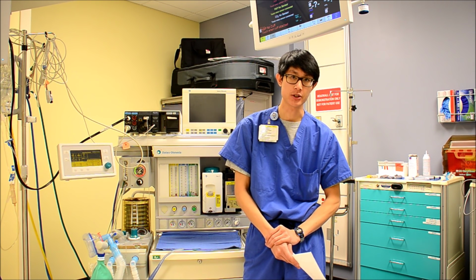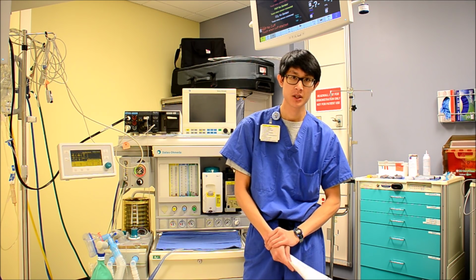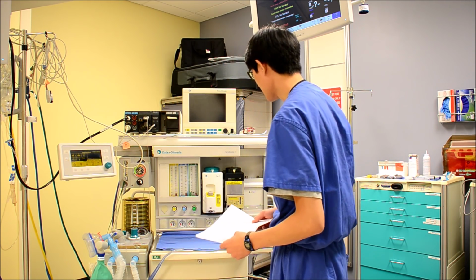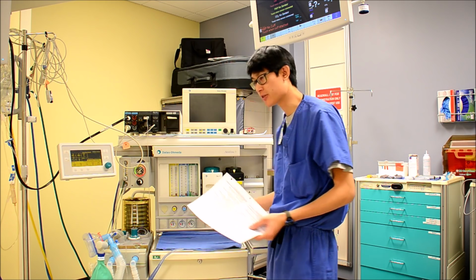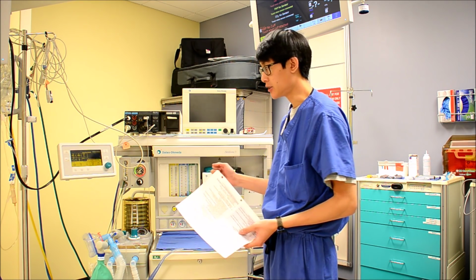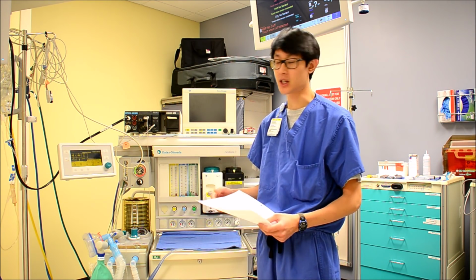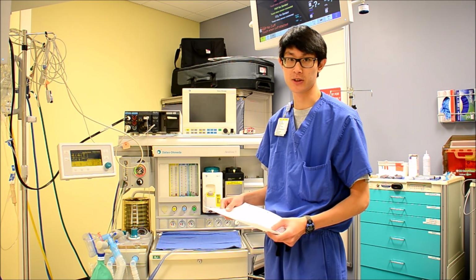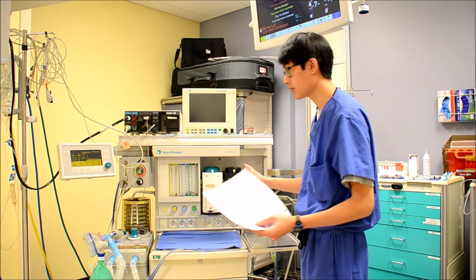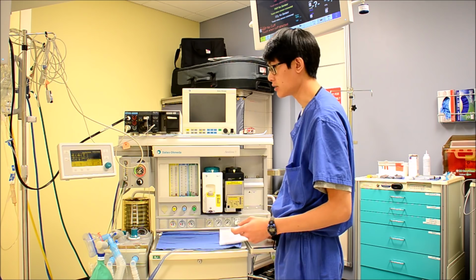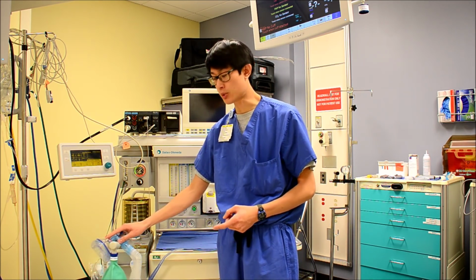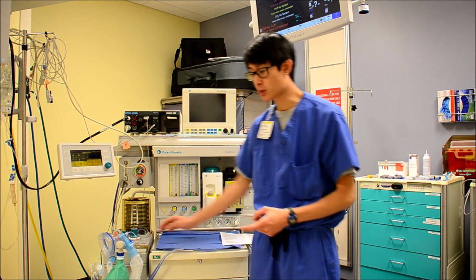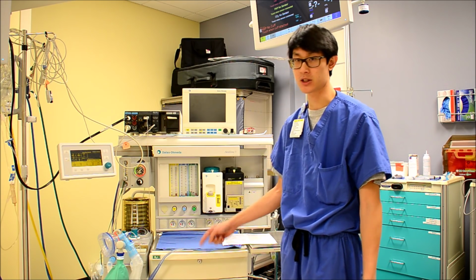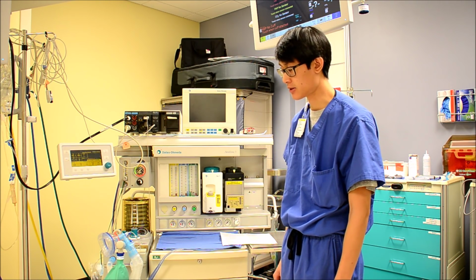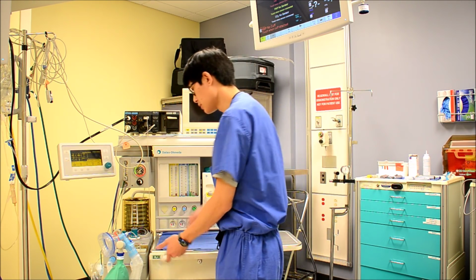So in between cases, you don't have to do the low pressure system check or the O2 calibration. If, in between cases, you end up turning your ventilator off, then you do have to recheck your low pressure and your O2 sensors. I would never do that in between a case. Just leave the ventilator on, and the only things you need to do is to check to make sure you can pressurize your circuit, the ventilator works, and that you have adequate suction, because they'll change all those items out in between cases. So just make sure.